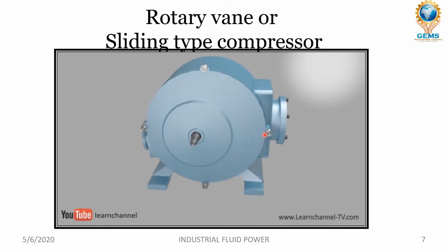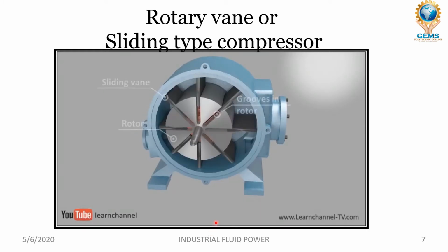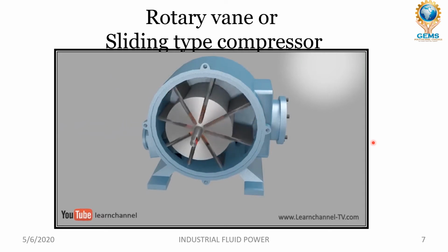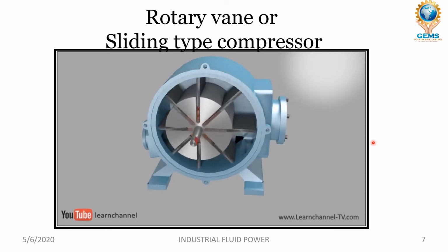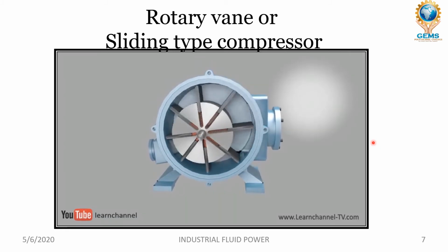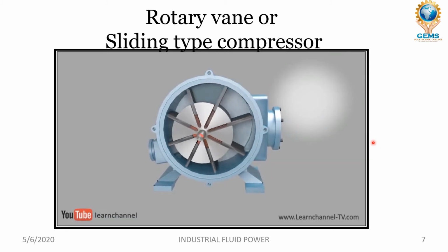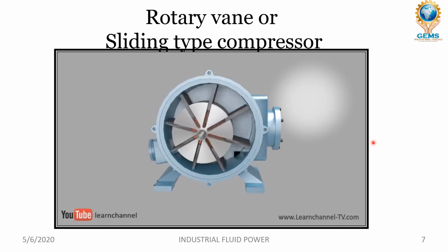A totally different working principle has the so-called rotary compressor, also named vane compressor. The typical rotary compressor has a cylindrical housing. Adjustable rotary vanes with their center point on an offset drive shaft have contact with the housing. When the shaft rotates, these vanes create chambers of variable sizes. Air is sucked into the largest chamber, compressed, and leaves the compressor at the smallest chamber.